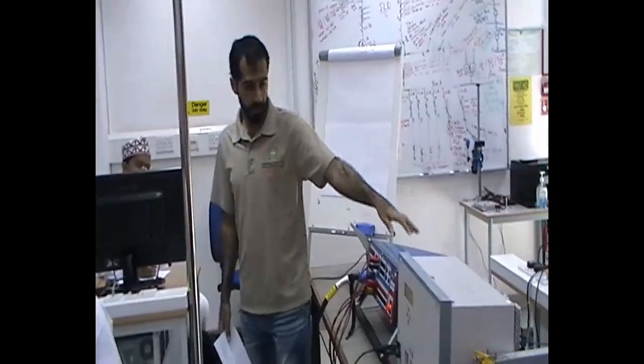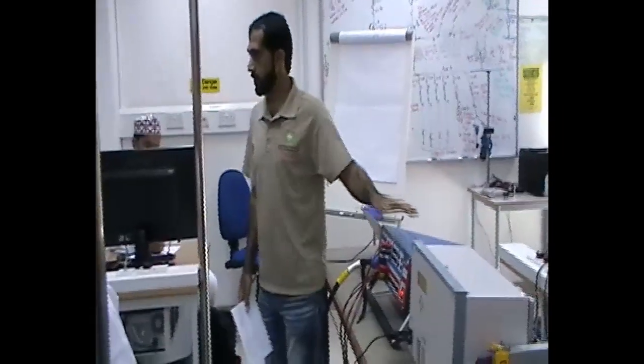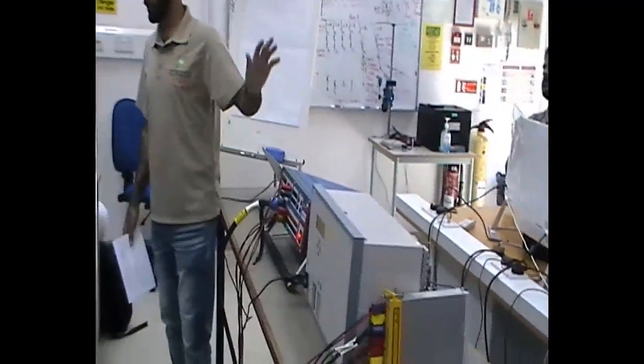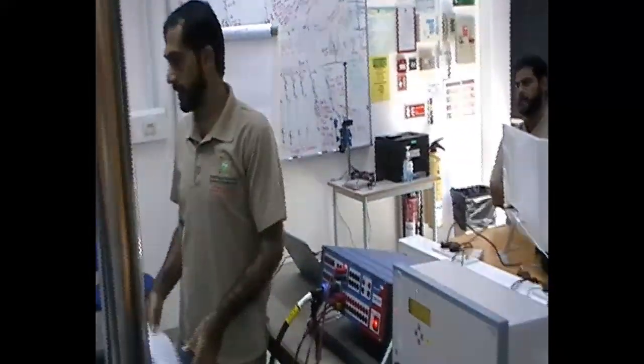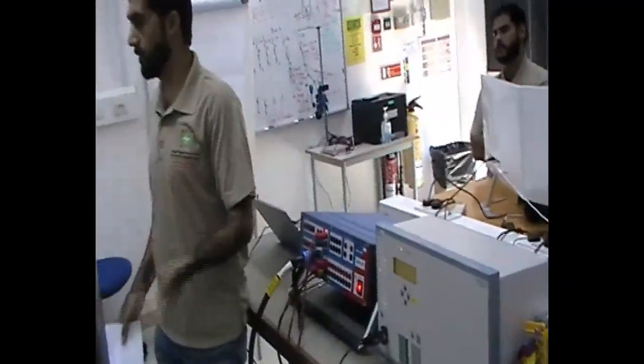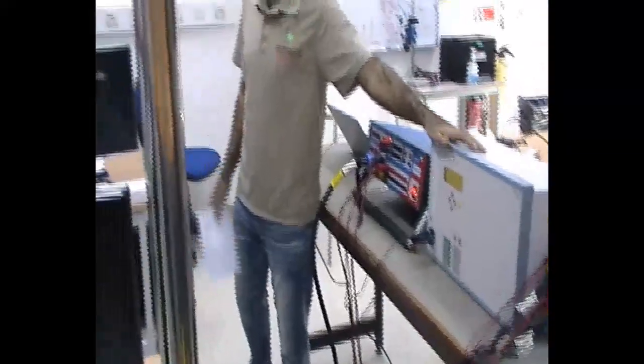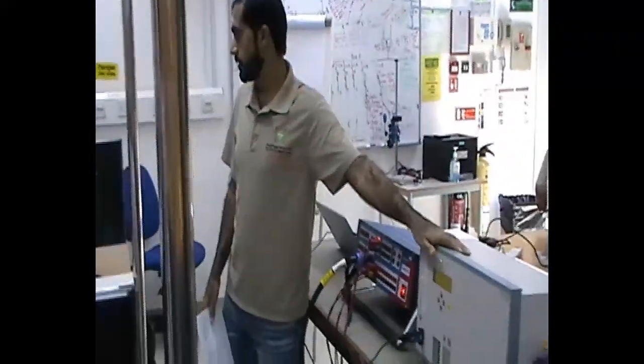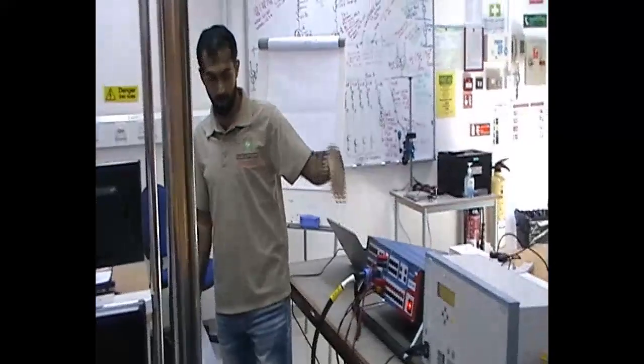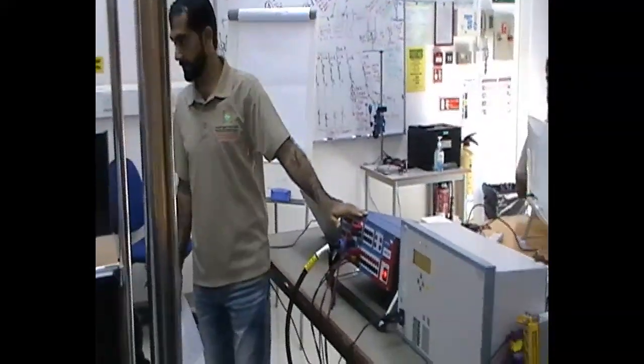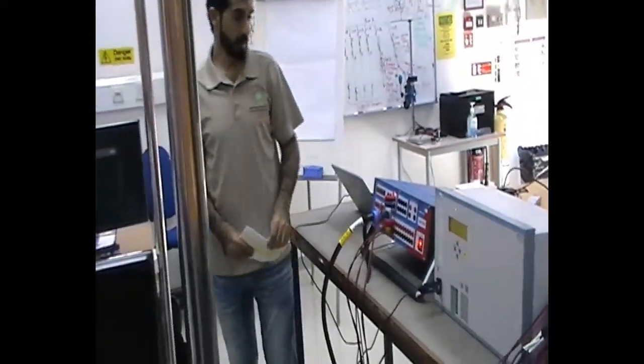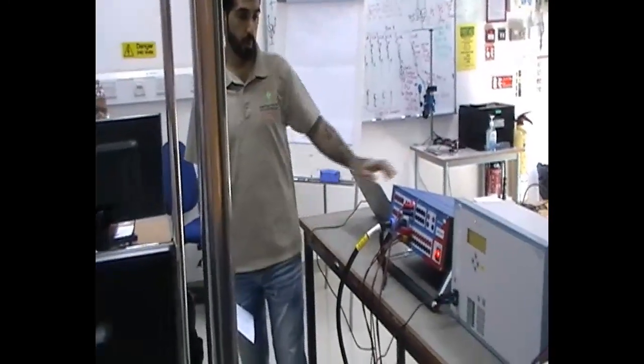Now, the second thing here, we have the Omicron device. It's one of the best testing kits in the market. It's a secondary injection, because what we are testing is a secondary device. We're not in the real high voltage system, neither 11 nor 33 kV. All the voltage here is like 110 volts DC, and the maximum current during a fault goes to about 20 amperes. So this is a secondary testing kit, because it cannot inject very high voltage or high current. Normally it goes up to 10 amperes, and the voltage goes up to almost 220.